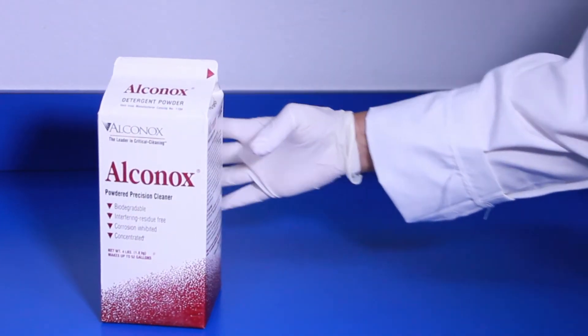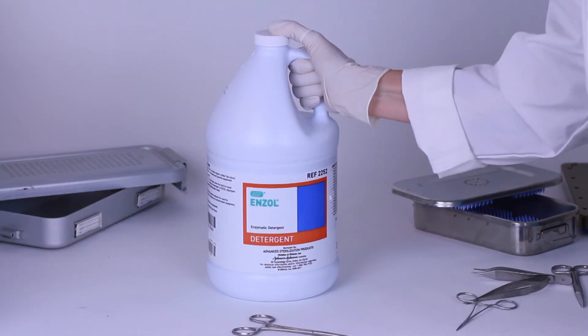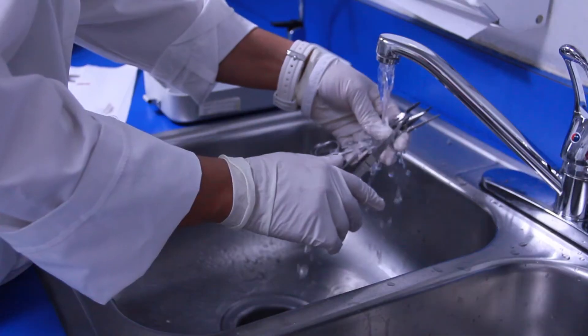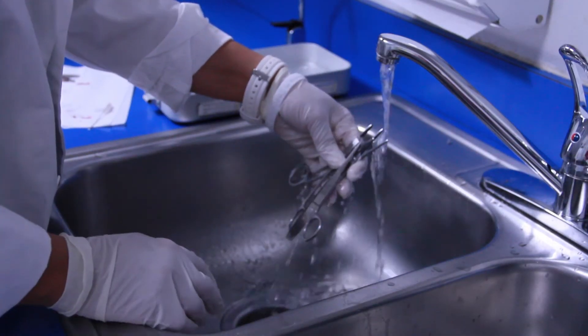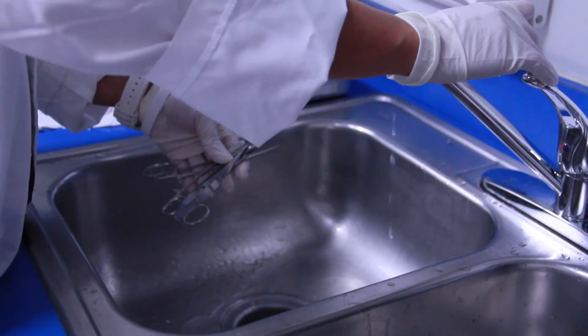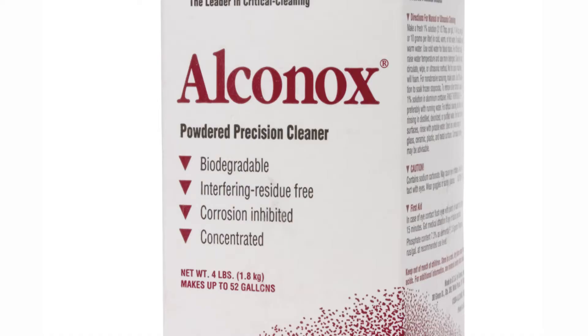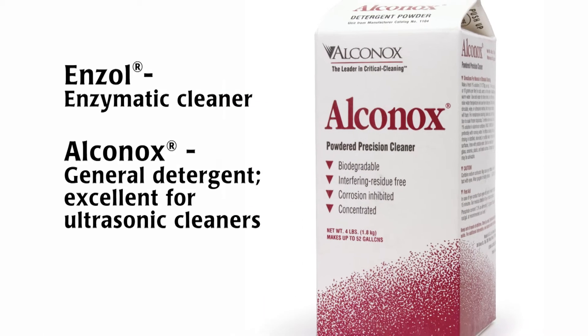You can clean surgical instruments manually or mechanically using water and detergents. An enzymatic detergent is helpful for removing biological contamination on instruments. Thoroughly clean your instruments, because any remaining debris can interfere with further sterilization and can corrupt research data. For best results, use a detergent like Enzol or Alconox.